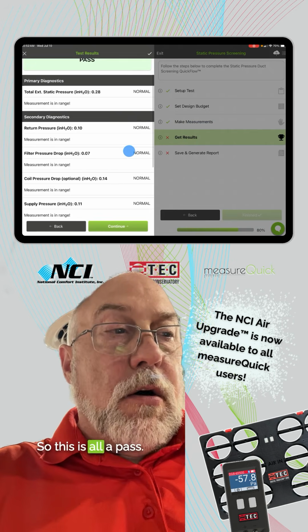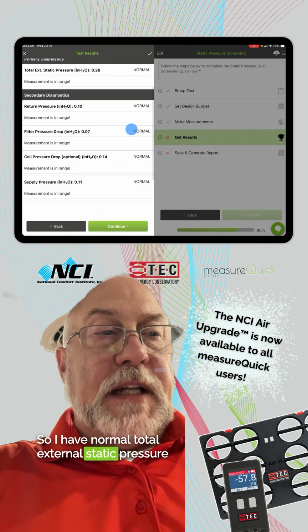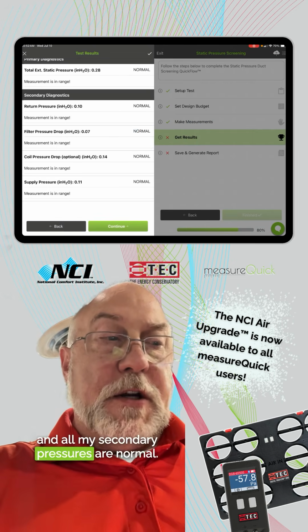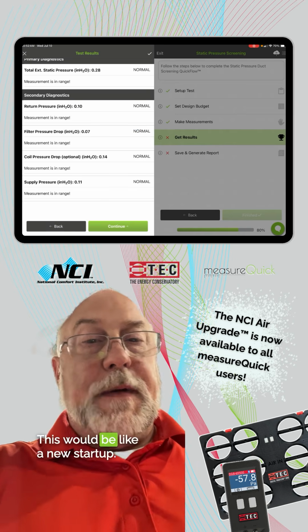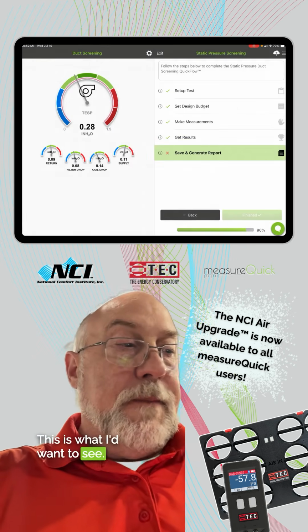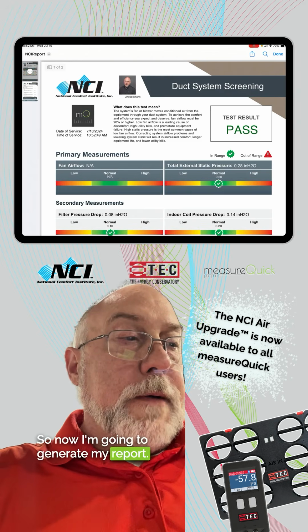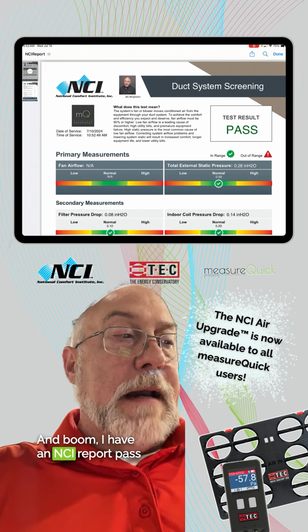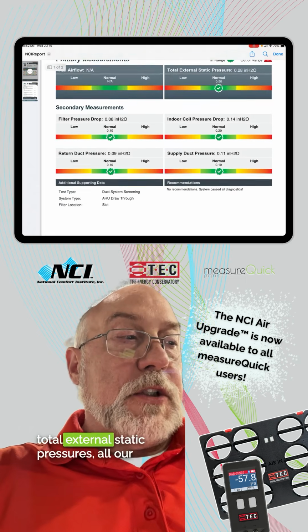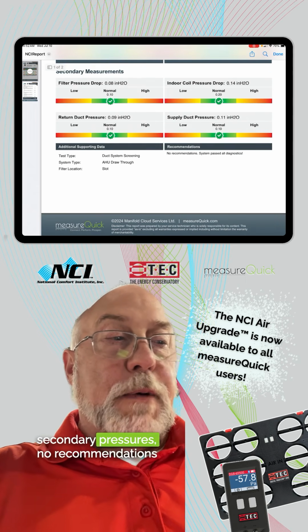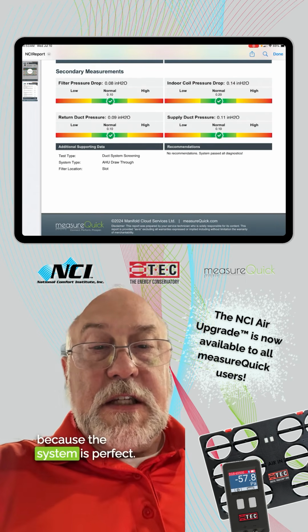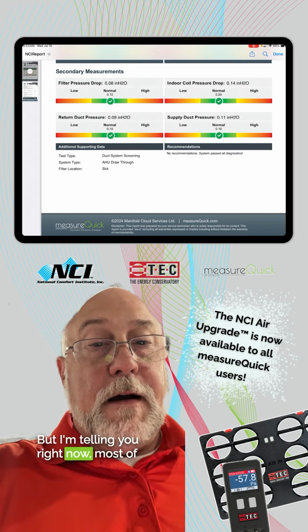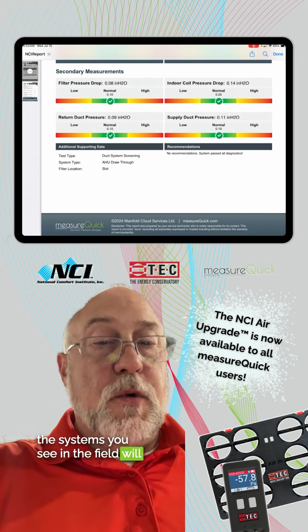So this is all a pass. So I have normal total external static pressure and all my secondary pressures are normal. This is perfect. This would be like a new startup. This is what I'd want to see. So now I'm going to generate my report and boom, I have an NCI report, pass, total external static pressures, all our secondary pressures. No recommendations because the system is perfect, but I'm telling you right now, most of the systems you see in the field will not be this way.